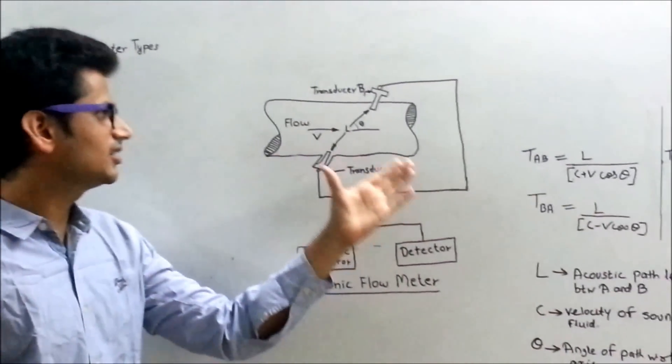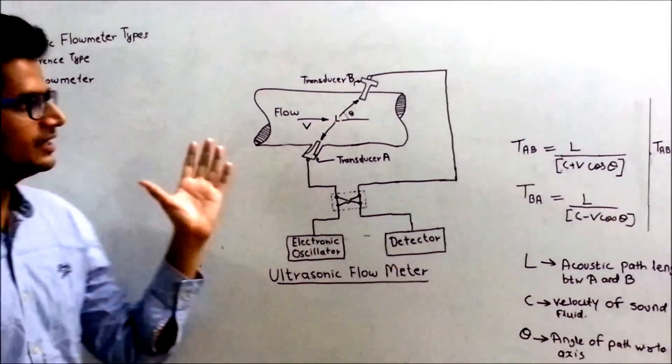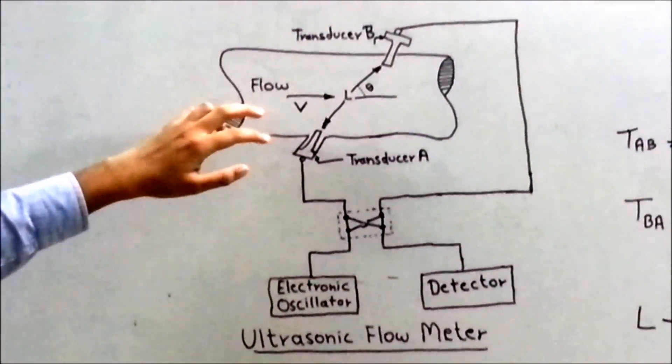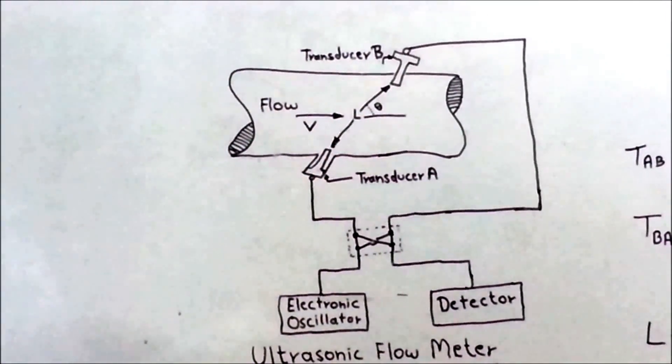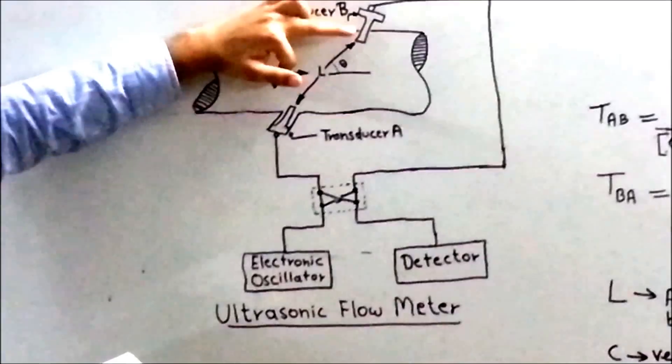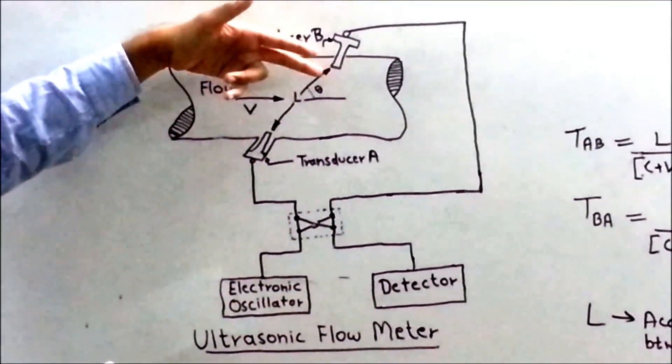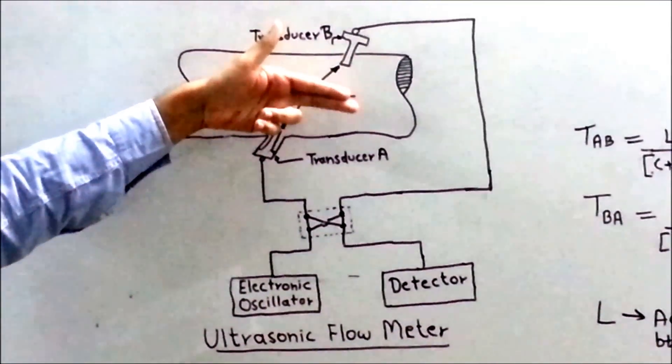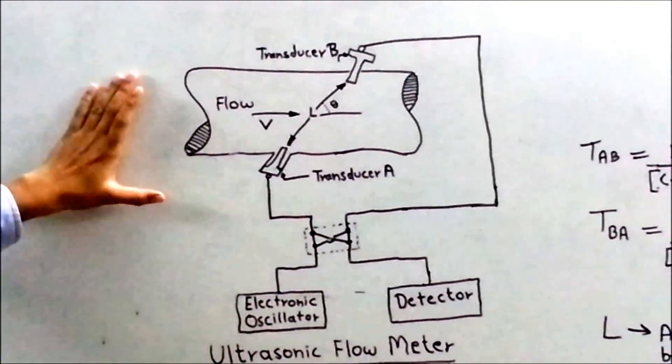As you can see, this is the setup of Ultrasonic Flowometer and its operating principle is based on Time Difference Type. This device measures flow by measuring the time taken for ultrasonic wave to traverse a pipe section both with and against the flow of liquid within the pipe. This was the working principle.